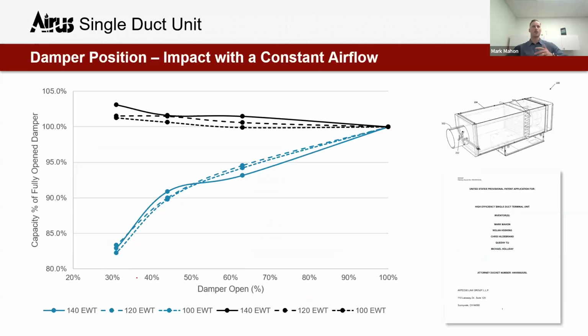So what is the result of this? Well, we can see the Airus in black here versus a commodity, traditional single duct unit in blue. As we move with a constant airflow through a variety of damper positions from 100% to a test point at about 65 to about 45% and down to a minimum of about 30%, we can see the Airus product maintains its heating performance, and actually, because of back pressure, it gets a little bit of a boost as the damper gets more shut, where a commodity traditional single duct is going to continue to have that performance deteriorate as the damper gets more and more closed.